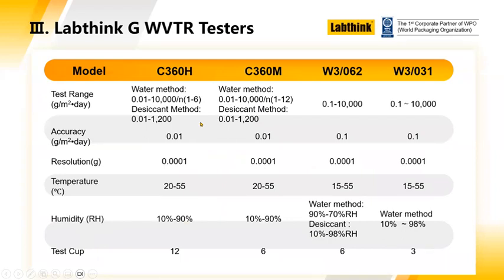So for different methods, you have different test ranges. If we look at the 360M, which is one of the more popular instruments, you can have 0.01 to 10,000 grams if you're using the water method, or 0.01 to 1,200 grams if you're using the desiccant method. The accuracies, as I said, were 0.01, 0.01, 0.1, and 0.1. I'm not concerned with the resolution. It's a very high resolution. Temperature ranges are around 15 to 20 up to 55 Celsius, and then a range of adjustable humidity conditions.